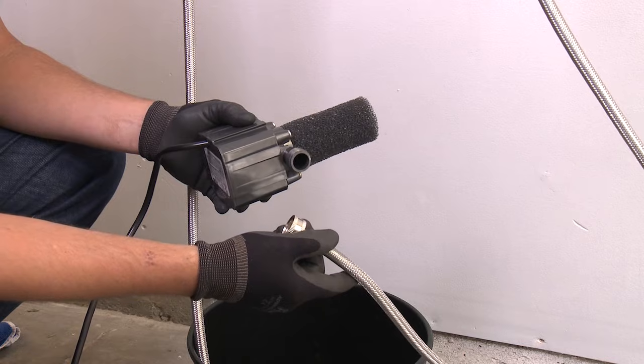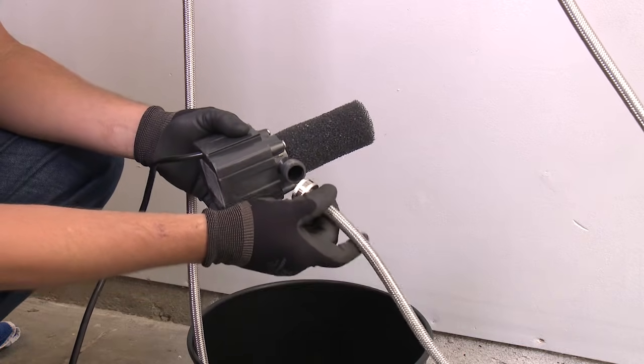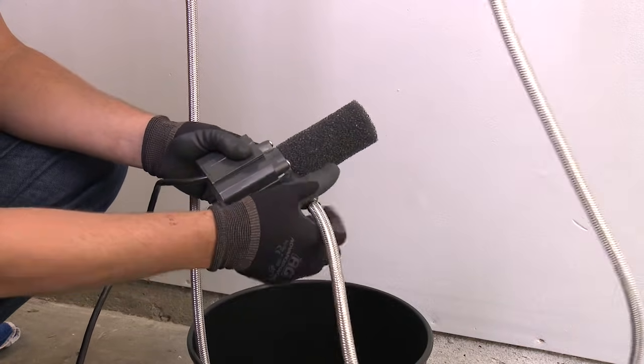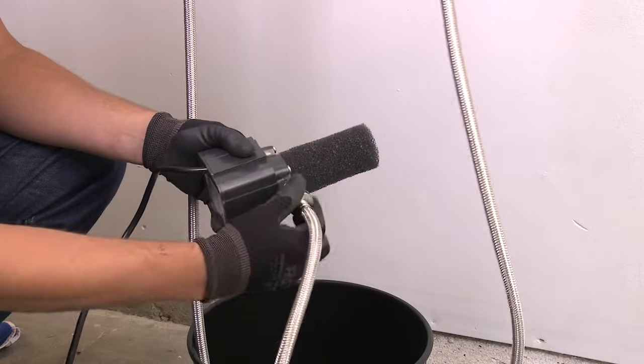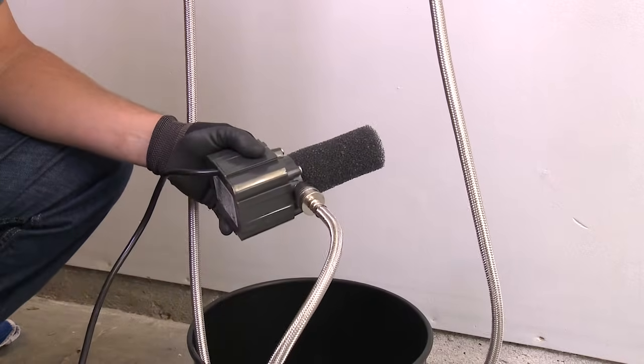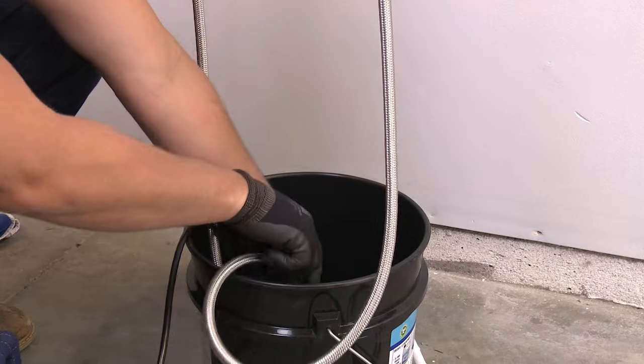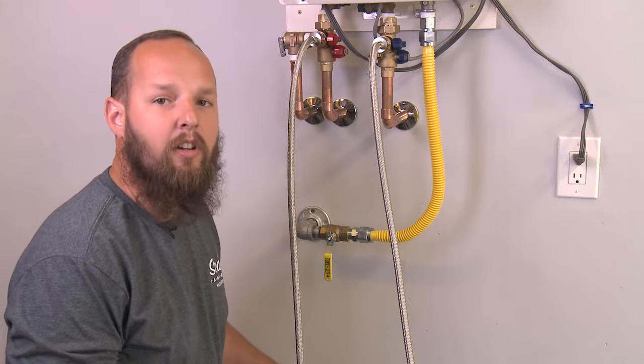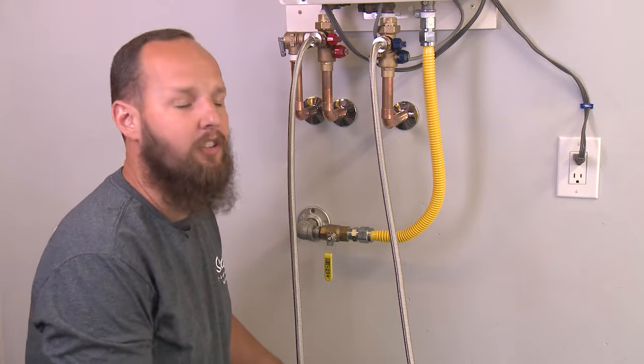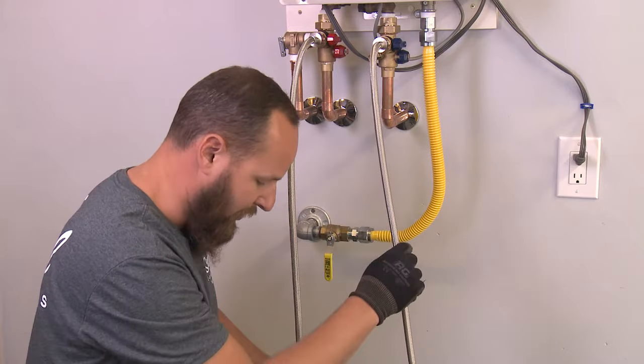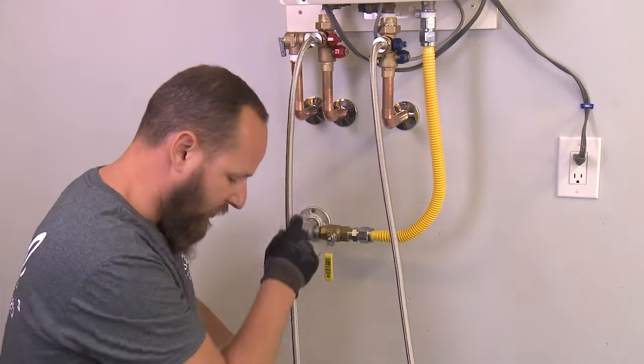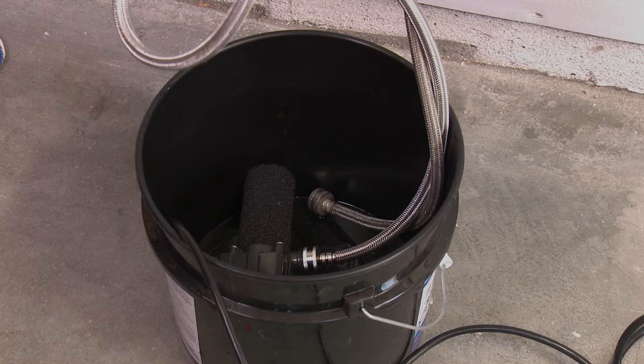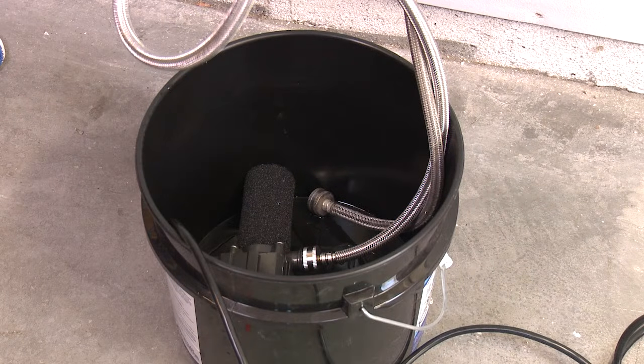Now we're going to connect the hose coming from the cold side of the water heater to the outlet of the pump. And place in the bucket. Now that we've got our pump and hoses set up, let's double check and make sure that our cold hose is connected to the pump and our hot line runs back down into the bucket. So now we'll fill the bucket up with water so that the pump is fully submerged.